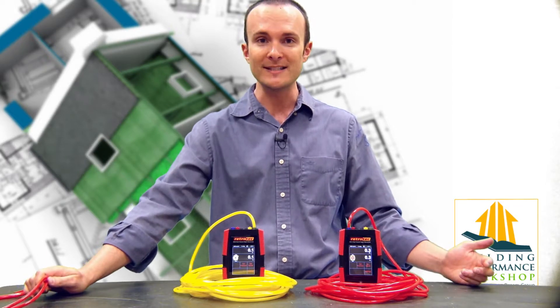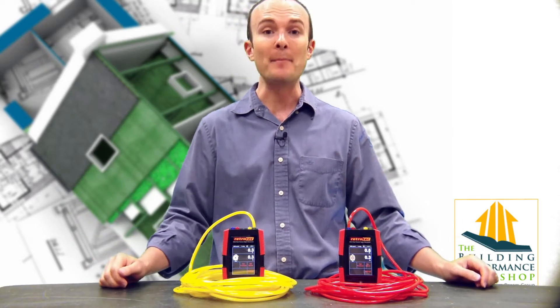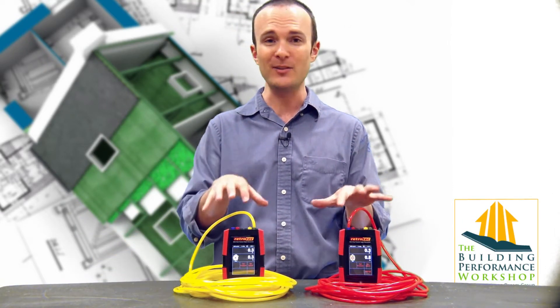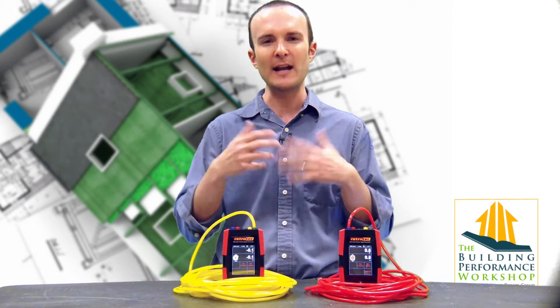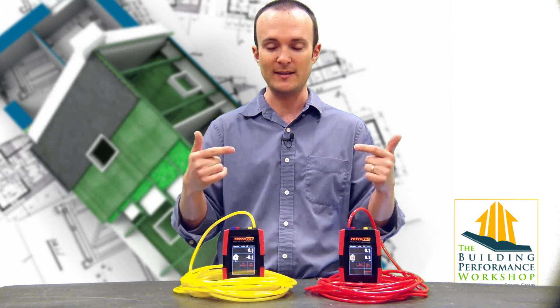These hoses and manometers are subject to inaccuracy. A manometer needs to be recalibrated, and these are the new smart gauges from Retrotec. They only need to be recalibrated every five years — that's a good thing. I can check them myself just to make sure that they're kind of in the neighborhood. If I've got several of them, I can link them together and see if they're reading the same thing.